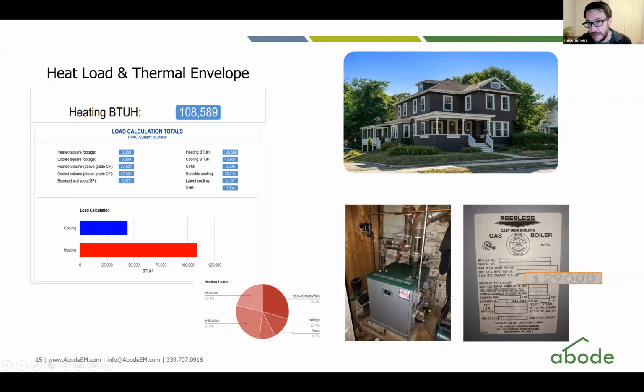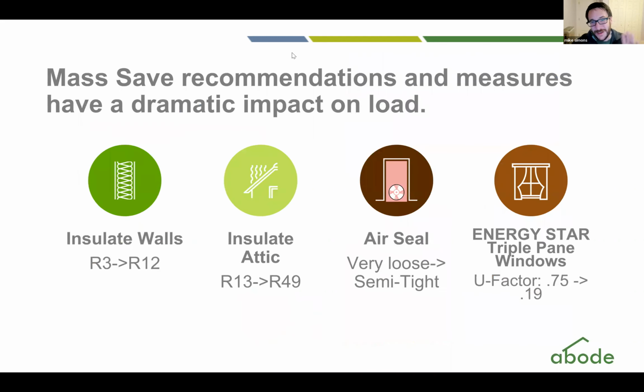So what I need is a system that can replace all of that energy that's being lost. And when I looked at my steam boiler, I saw that the boiler could provide 129,000 BTUs per hour. So 129,000 is slightly bigger than 108,000, so my home would heat. Say a polar vortex hung over Leominster and it was negative 15 degrees for 72 hours in a row, this steam boiler would still be running, it would still be operating, but I wouldn't be able to maintain 70 degrees. So this is going to be a key concept as you are thinking about heat pump sizing in a second. But let me go back.